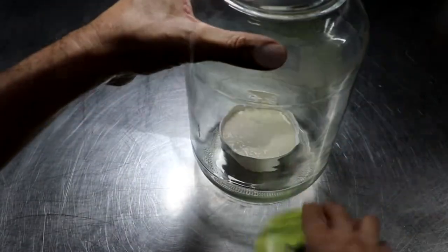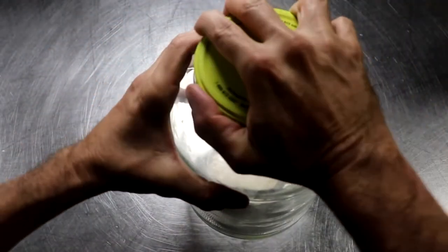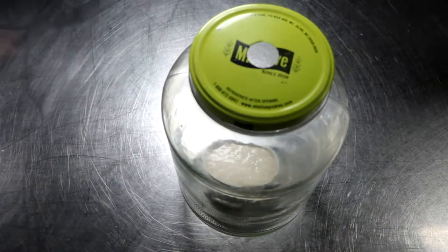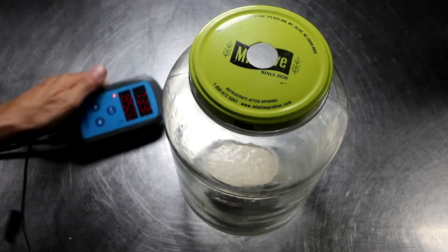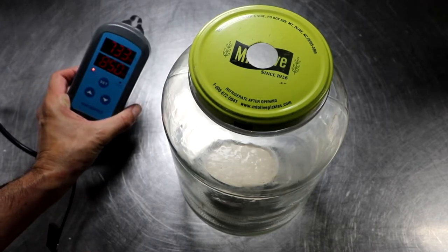Having this ratio of salt to water is going to provide a 75% relative humidity environment inside that jar, which is going to give us the opportunity to calibrate our equipment. I try to calibrate my equipment roughly once every six months.